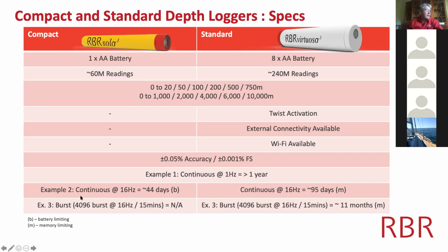But after, for example, in continuous mode at 16 Hertz, it's 44 days of deployment for the solo, and 95 days for the standard. Here, the limit is the battery. Here, the limit is the memory. It's very different. And in example 3, we don't have access for the solo, but we have access with burst mode for 11 months with the standard logger.